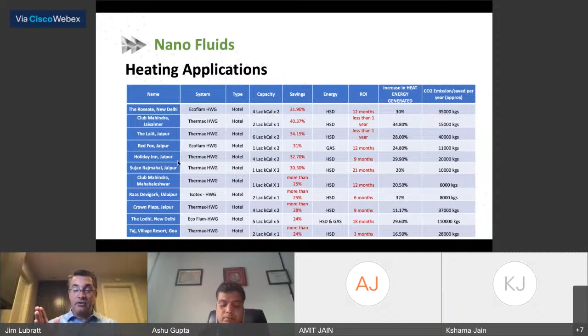Again, the difference here is that we're increasing the heat transfer performance of the equipment, not just the boilers in this example for heating, but also the coils, the fan coils, the air handlers that it serves. And then, also highlighted in red, the ROI, return on investment - as you can see, most of these are under 2 years. So it's a very successful installation, and perfect for the ESCO model, for ESCO contractors to use a nanofluid to save energy with this very fast return on investment.